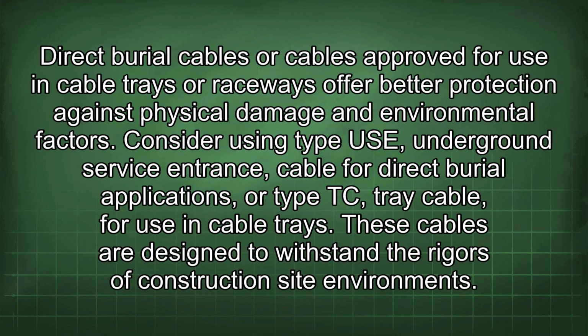Direct burial cables or cables approved for use in cable trays or raceways offer better protection against physical damage and environmental factors. Consider using type USE, underground service entrance cable, for direct burial applications, or type TC, tray cable, for use in cable trays. These cables are designed to withstand the rigors of a construction site environment.